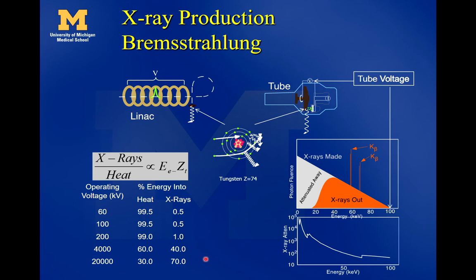Other departments may run differently — sometimes running the electron beam helps get all the other parts of the linac warmed up. And in a graph of x-ray production, the orange curve shows the x-rays that actually make it out of the x-ray tube versus the number actually produced. The tube voltage determines the maximum x-ray energy that can be made in the x-ray tube.